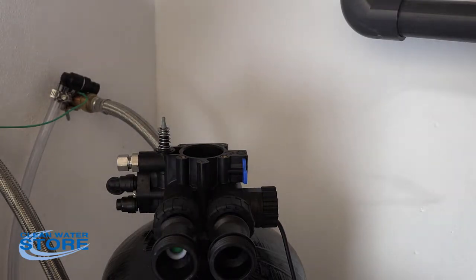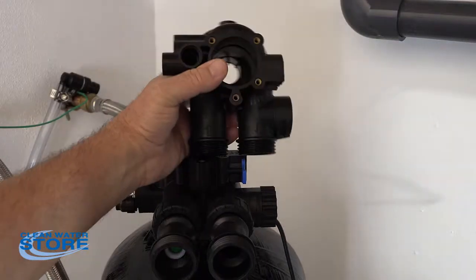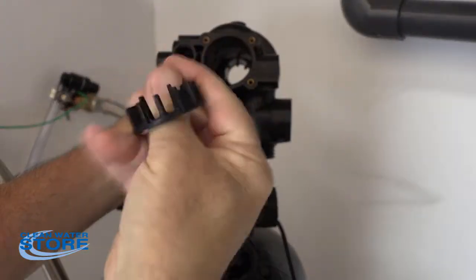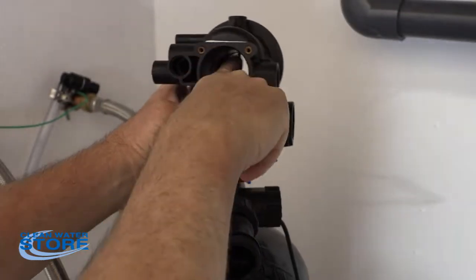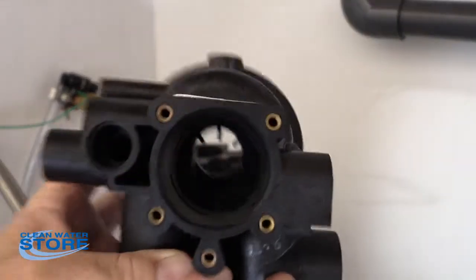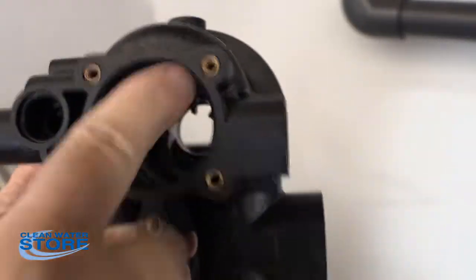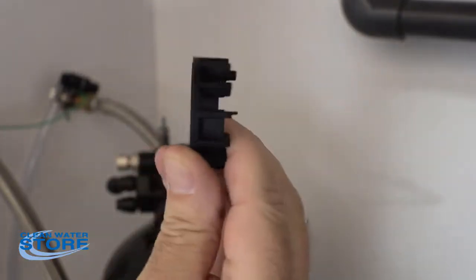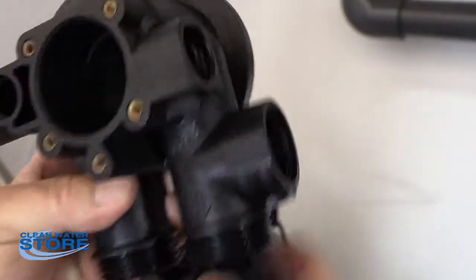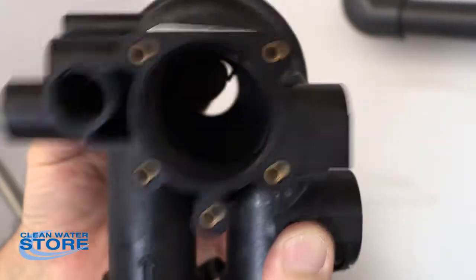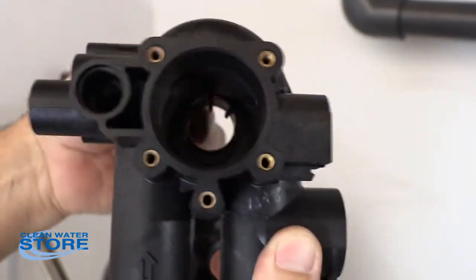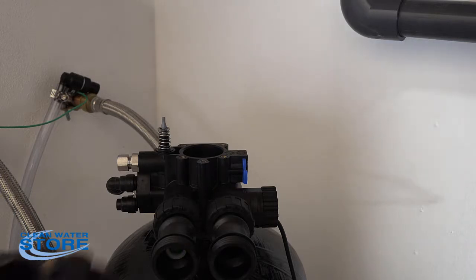I do have a valve body here and I wanted to show you the front of the valve. There's two little holes in here and these little tangs need to line up with those little - you can see the little tangs here on this guy. Right here, these two sticking out, need to line up back up into here where these are. So right up into this area. Make sure that bottom seal gets up in there and again that's facing the front of the valve is where that ends up clocking in.